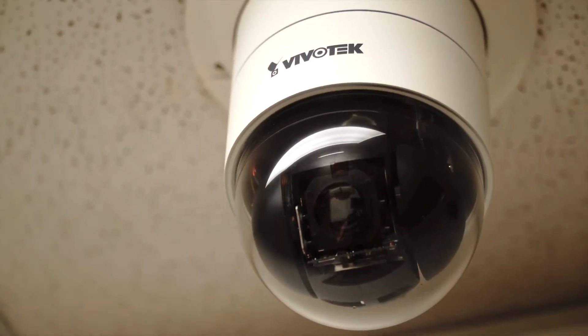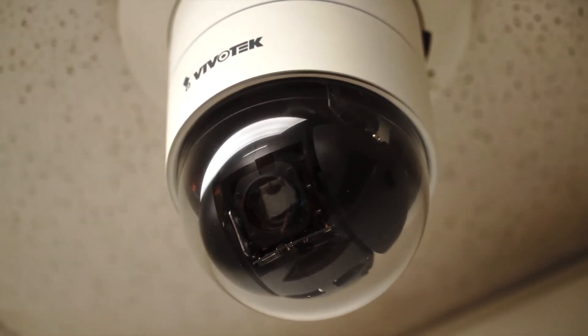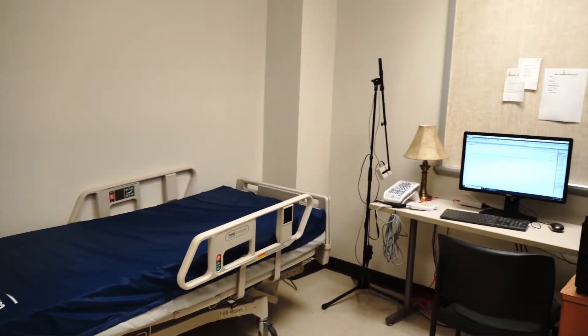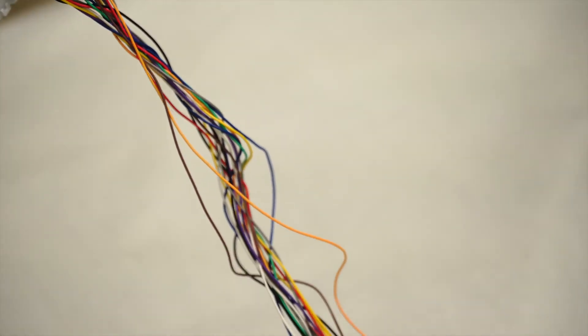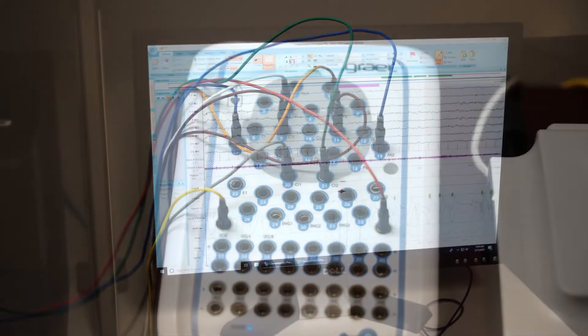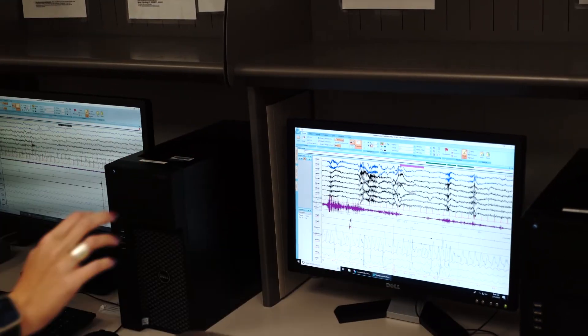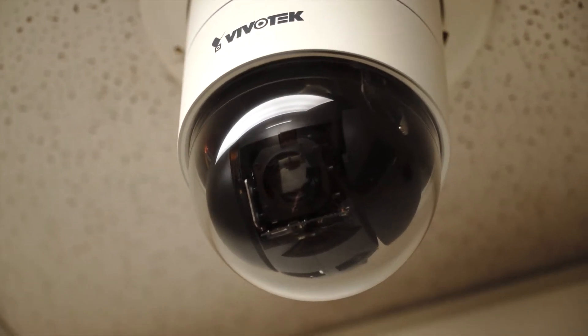Each sleep lab also has a video that we can monitor our patients with and an intercom, and we have a control room for our students. We also have a six-bed mini sleep lab that our students use during lab time. The equipment and software allows us to apply the electrodes necessary to run a sleep study. We plug all of our electrodes into a head box that then takes that signal through an amplifier and displays it on the computer as a waveform for our students to read. Our students can monitor the patient from the computer as well as observe them from the video system and intercom.